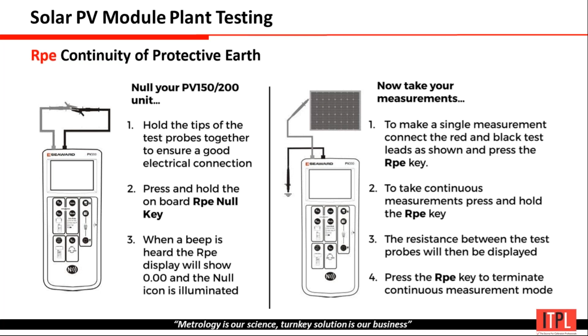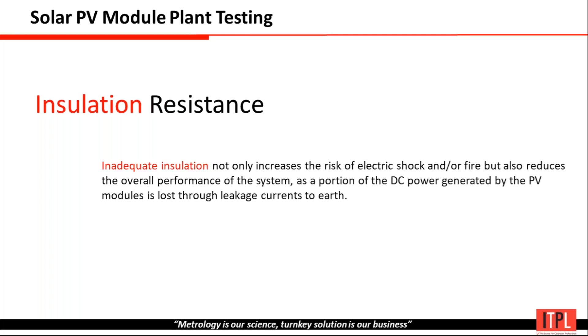Then the second one is the insulation resistance. Insulation resistance is also a part of the safety parameters. As we all know, we use a Megger in our power plants at 1 kV, 2 kV, 2.5 kV, 5 kV, and 10 kV and so on. So in our solar power plant, we are also measuring insulation resistance up to 1 kV and 2 kV and maximum up to 5 kV. This is also a safety aspect parameter.